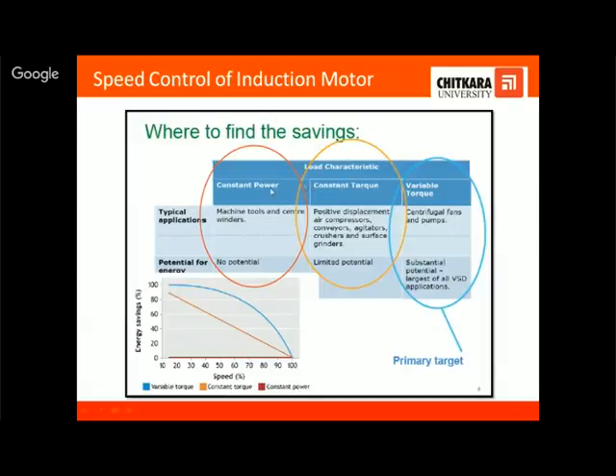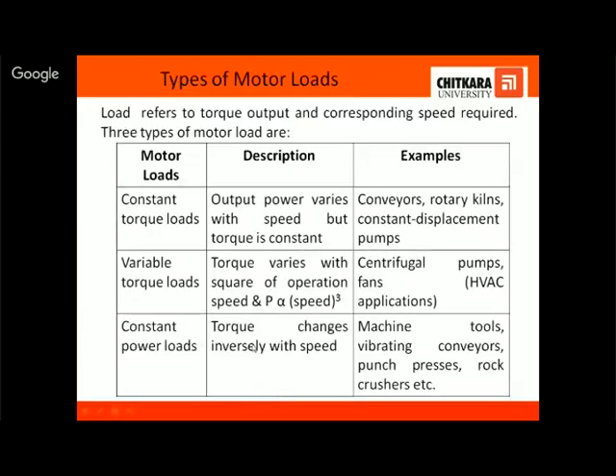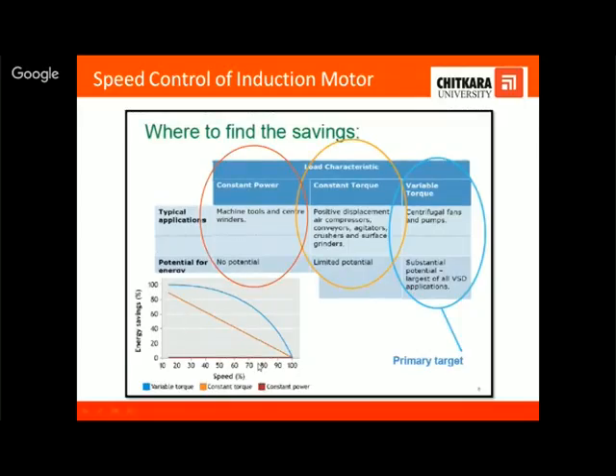Now, if we see constant power, constant torque and variable torque, and find out the energy saving against the speed, we find that for constant power loads, where torque changes inversely with the speed, there is hardly any scope for energy saving. So maximum saving is here, that is the variable torque. Even constant torque loads offer some opportunity for energy savings. So it means centrifugal fans and pumps have the maximum potential for energy saving, where we use variable speed drives.